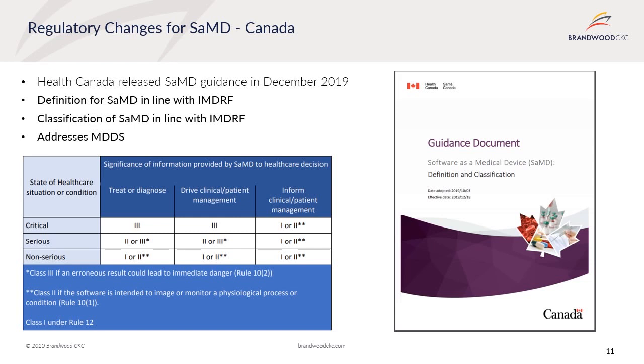In Canada, in December 2019, Health Canada published their guidance document on software as a medical device. Similar to the EU and Australia, Canada also adopted the IMDRF framework for software as a medical device, including the definitions we spoke about earlier, and classification based on the significance of the information provided by the software to a healthcare decision and on the state of the healthcare situation or condition. The classifications are defined within the current classification Rule 10 and 12, with low-risk software classified as Class 1 and higher risk as Class 3.